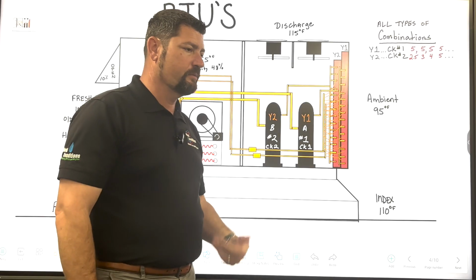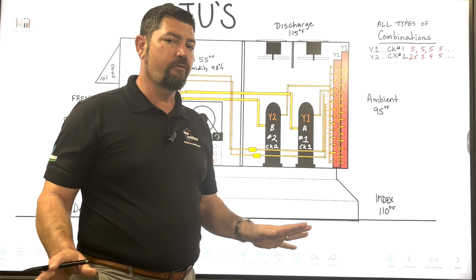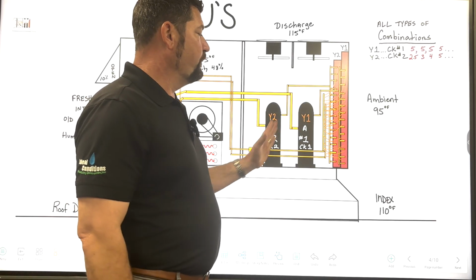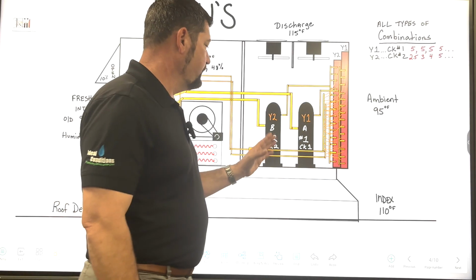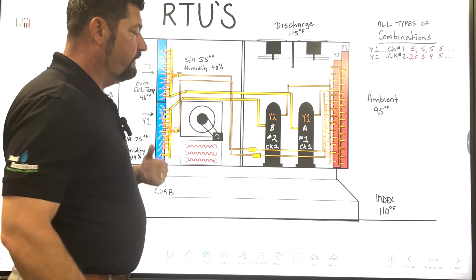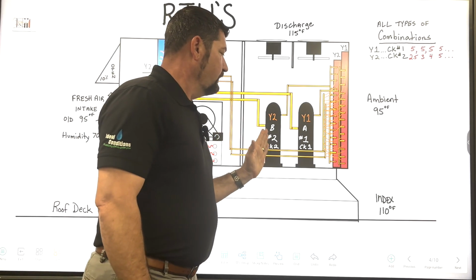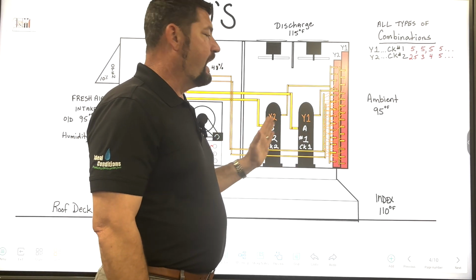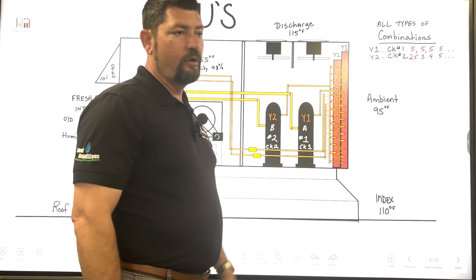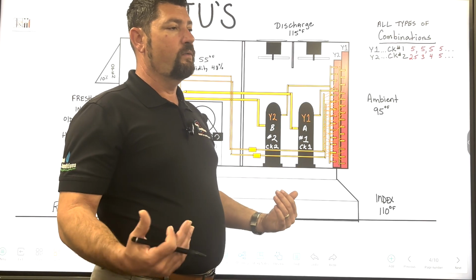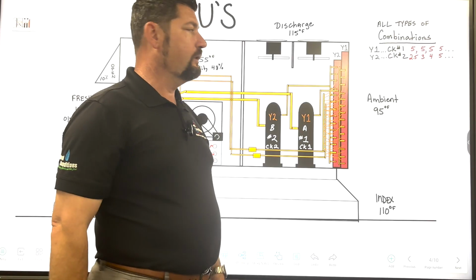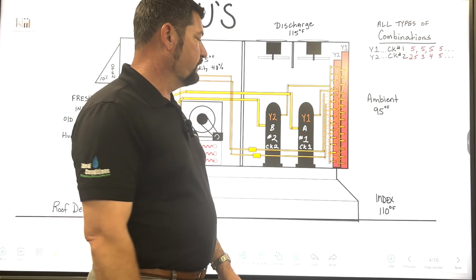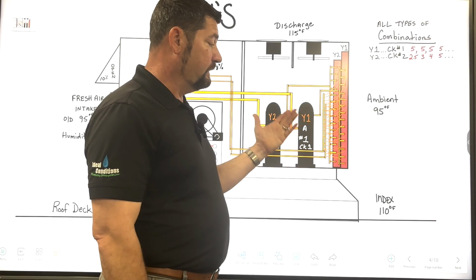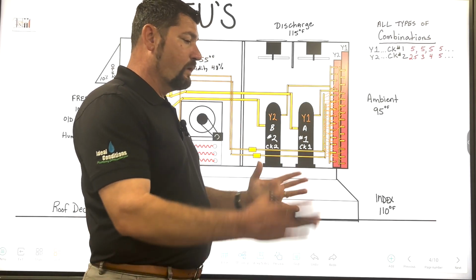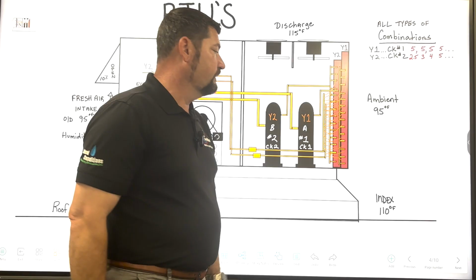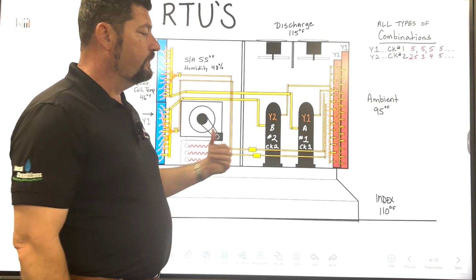So if you have one customer that's saying, hey, the humidity is high, the very first thing I would be checking is, do both compressors come on and run? Am I running Y2 only? Okay, if that's not the case, if they both do run, how do they sequence? Does Y1 come on by itself? Or did somebody put Y1 and Y2 in the same bus bar on the thermostat or wire them together up in the control panel of the RTU where they were just being lazy or whatever, and they didn't have Y1 and Y2 to where it could stage properly? A lot of times, that's just overkill and you're going to shorten the cycle.